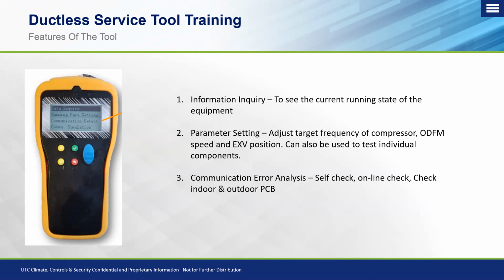If you were troubleshooting an indoor unit, this tool is essentially going to send a code and act as the outdoor unit and make sure the indoor unit responds. Vice versa, if you're using it to check an outdoor control board, the tool is going to act as an indoor unit, send a control signal to the outdoor unit board, and make sure you get a proper response back. And it's a really great way to narrow down whether you actually have a control board issue or if you're dealing with another factor that you need to focus on.